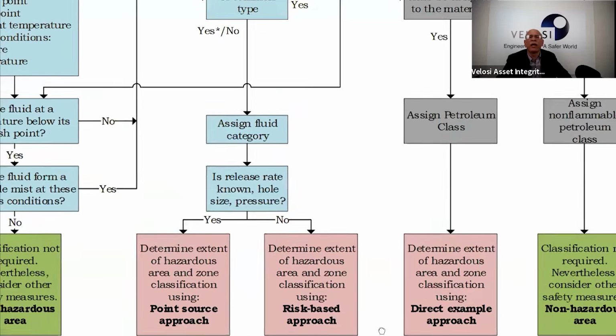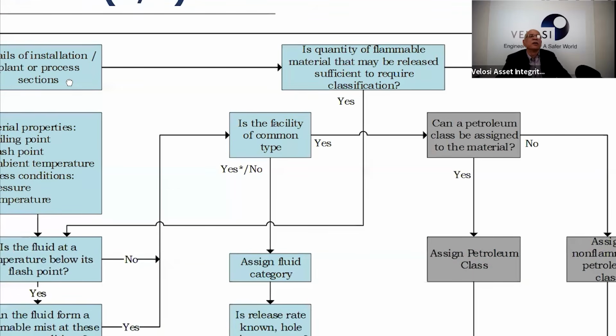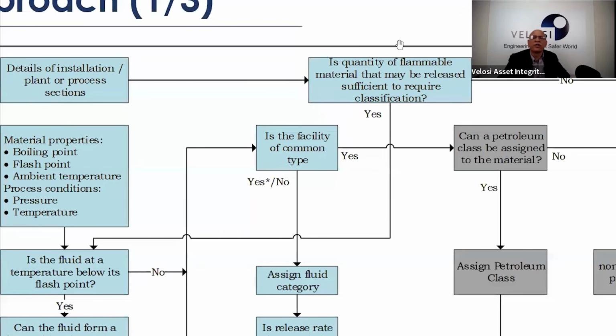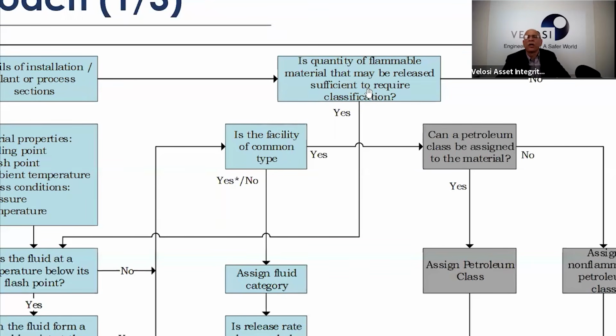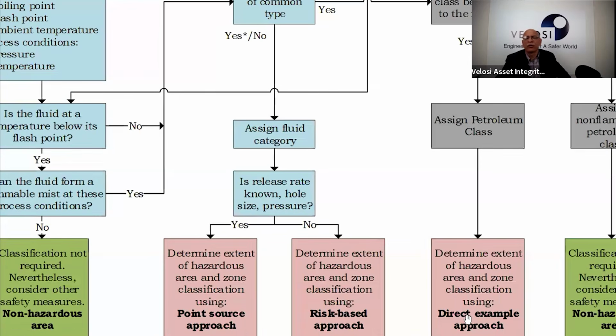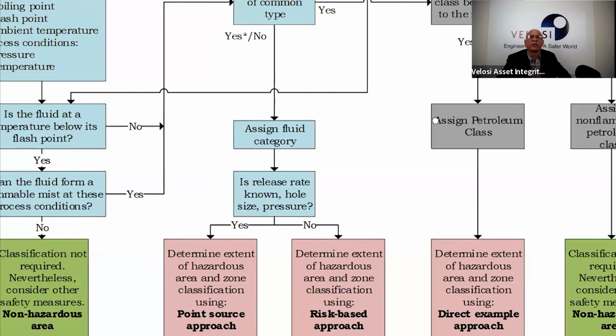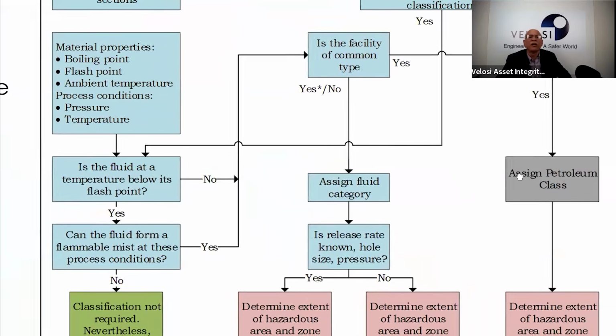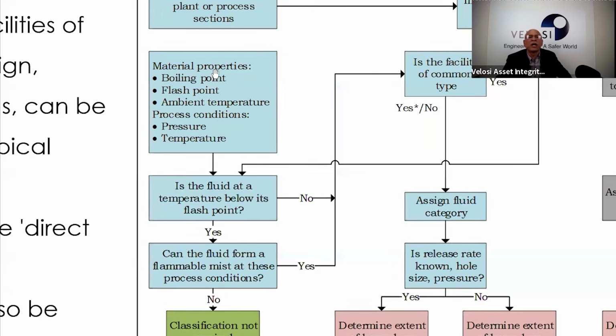So if I go back, take the details of any installation, plant or facility. Is the quantity of flammable material that may be released sufficient to require classification? No, then non-hazard area. If yes, is the facility of common type? If yes, can a petroleum class be assigned? Yes, assign the petroleum class, go to the direct approach, and do hazard area classification. If no, then we go to the bigger process. This is normally what we follow.